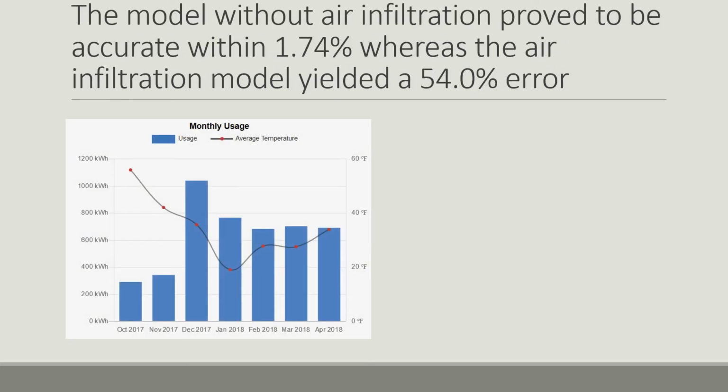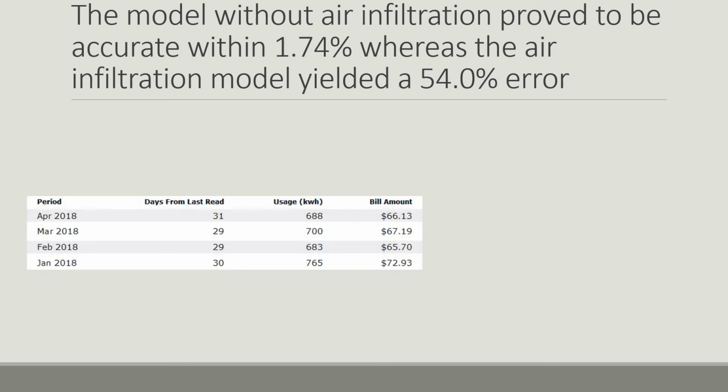The purpose of this project was to determine the heat loss in Josh's apartment. We felt very confident that we had done this, and in the spirit of wanting to see how closely our model could match this apartment, we looked at his monthly heating bill. This graph shows the amount of usage Josh had over the last several months, as well as the average monthly temperatures. We averaged the last 4 months due to their fairly consistent behavior and compared them to our two models.